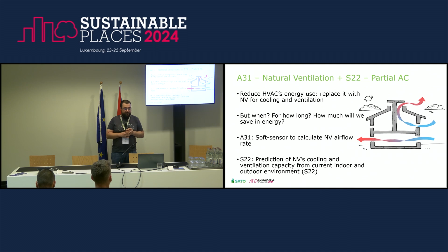In the context of the project, we have one assessment where we use a soft sensor to calculate the airflow of natural ventilation — you don't have a real physical sensor to measure that, you need some sort of algorithm to calculate it. Then we have a service where we predict the impact on savings based on current indoor and outdoor conditions and the soft sensor's estimate of flow. And then we decide whether to open windows or close them.